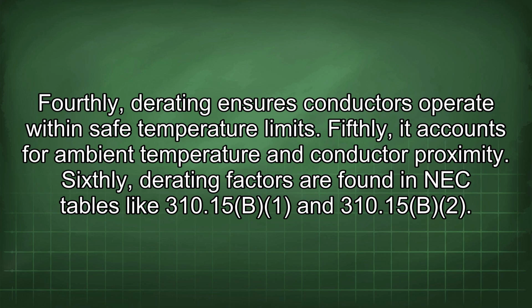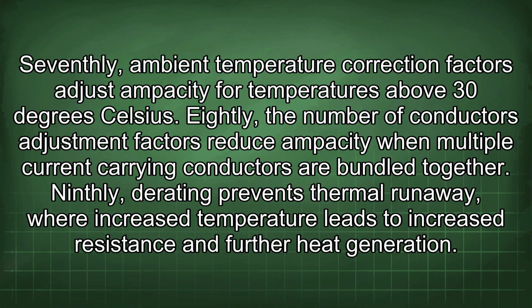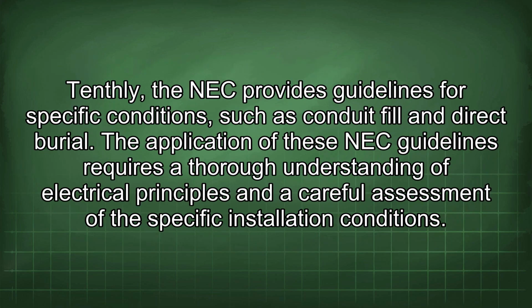Sixthly, derating factors are found in NEC tables like 310.15b1 and 310.15b2. Seventhly, ambient temperature correction factors adjust ampacity for temperatures above 30 degrees Celsius. Eighthly, the number of conductors adjustment factors reduce ampacity when multiple current carrying conductors are bundled together. Ninthly, derating prevents thermal runaway, where increased temperature leads to increased resistance and further heat generation. Tenthly, the NEC provides guidelines for specific conditions such as conduit fill and direct burial.